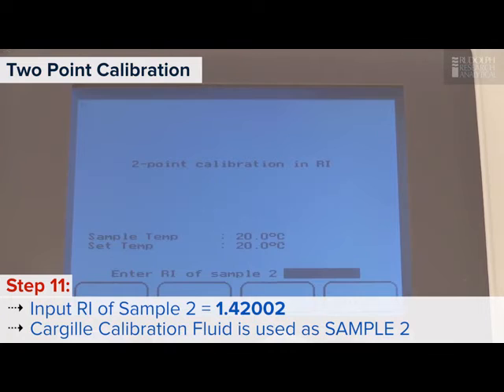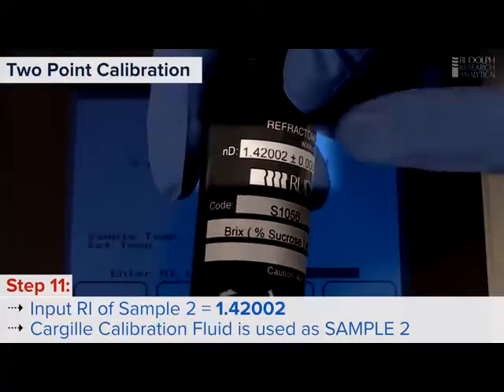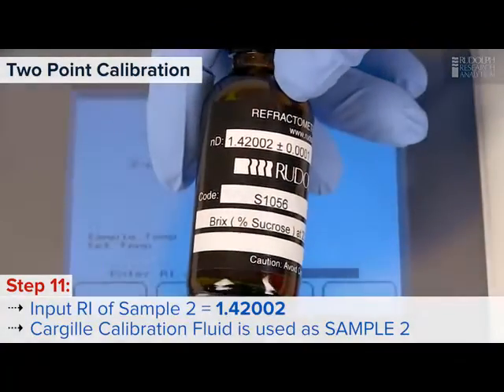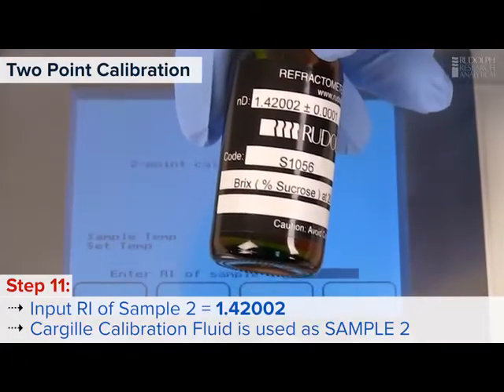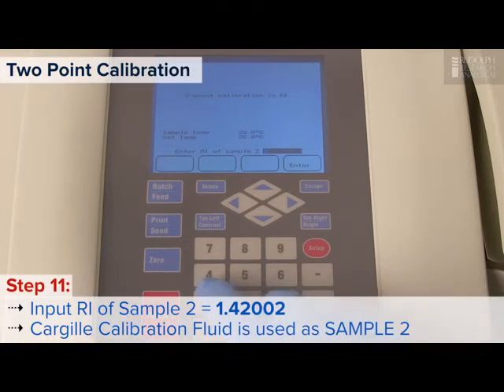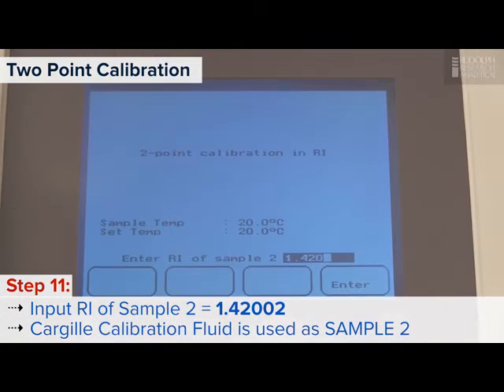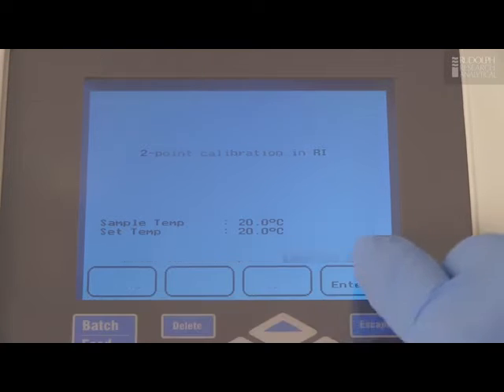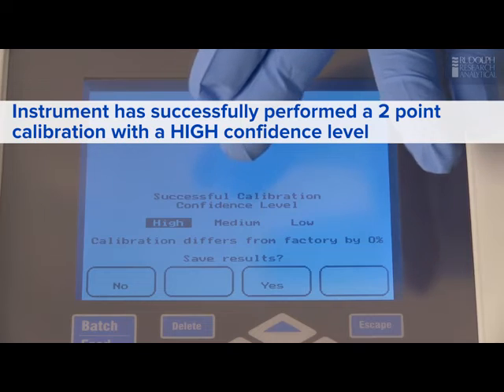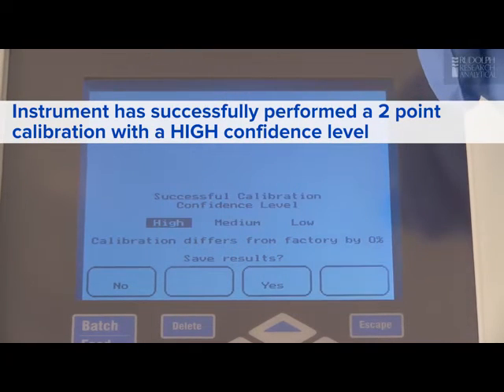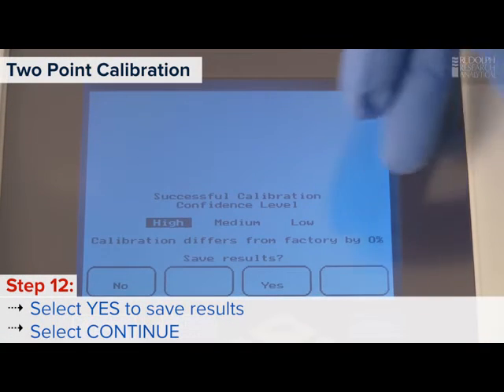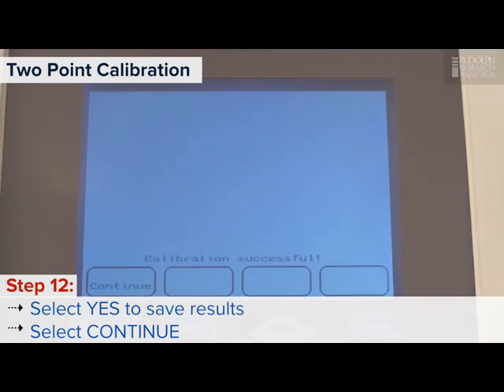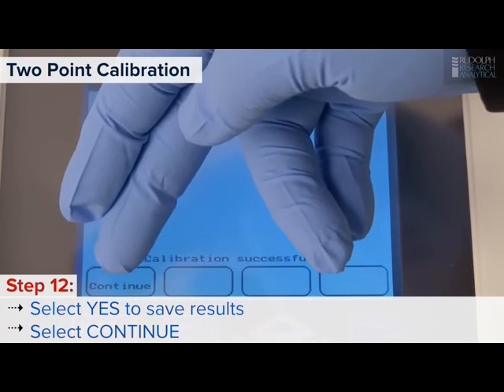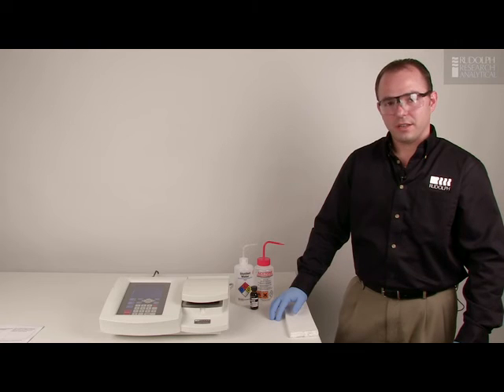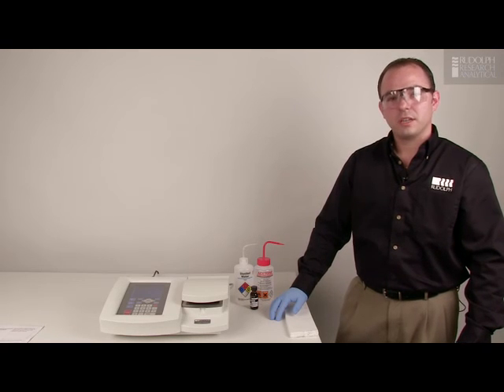The instrument will now ask you to enter in the RI value of sample 2. If you notice on the bottle, it's a value of 1.42002. We will now enter that into the instrument to complete the calibration. As you can see, the calibration was successful and you have a very high confidence level that your calibration was performed properly. At that time, you're going to save results. Yes. Calibration is successful. Press continue. We have now successfully calibrated the refractometer using a single point calibration and a 2-point calibration.